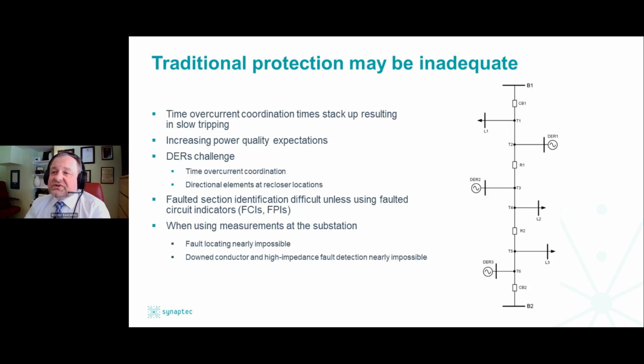So traditional protection may not be adequate. Obviously, the time over current coordination times stack up, and that means that we have a slower fault tripping time when the fault moves closer to a source, exactly the opposite of what we want. Then the power quality expectations are increasing because the loads are becoming more fragile.